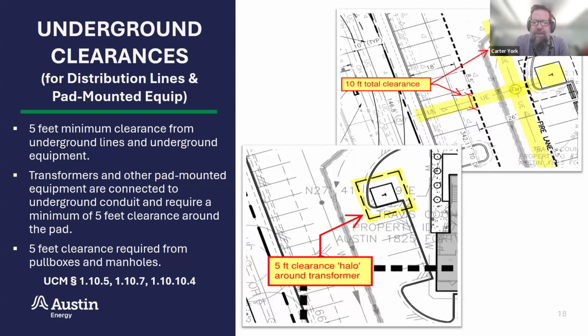The top right image shows a transformer that's highlighted with the yellow T on the far right side of the image. The dotted black line around that transformer is showing the 5-foot clearance halo that needs to be clear. As you follow the highlighted lines from that transformer, represented by the line with UE for underground electric, we need 5 feet of clearance on each side of that line for a total of 10 feet clearance that covers both sides of all of that underground conduit.